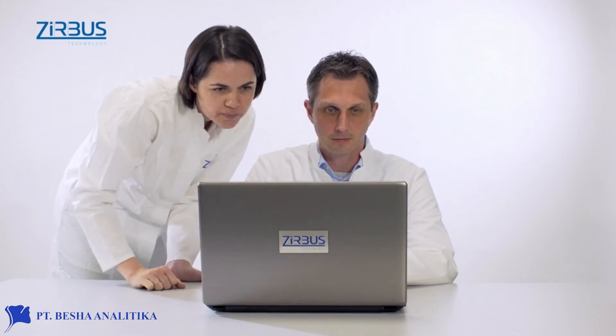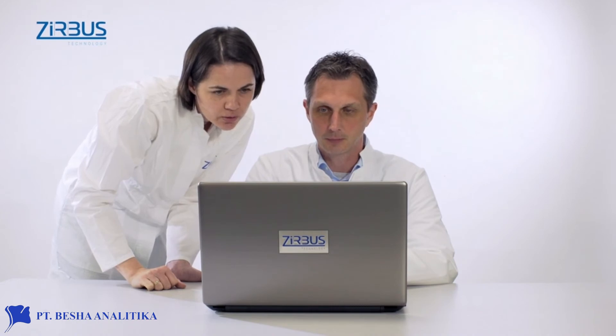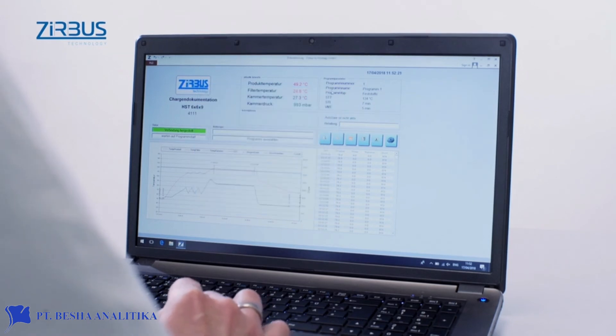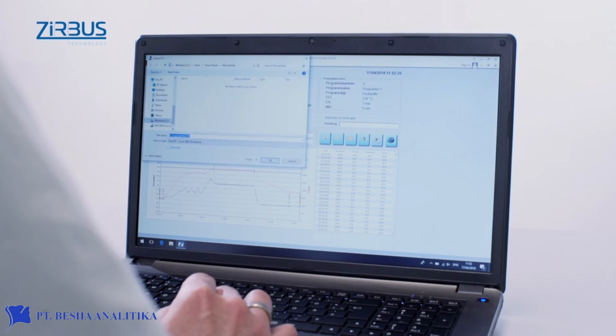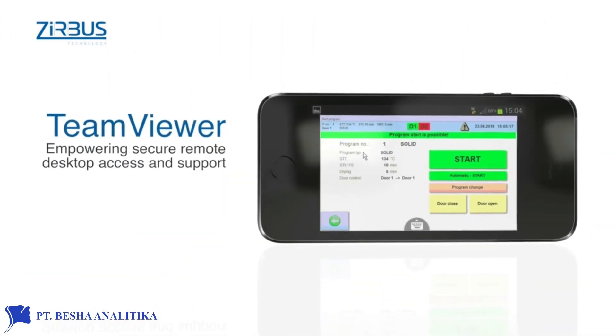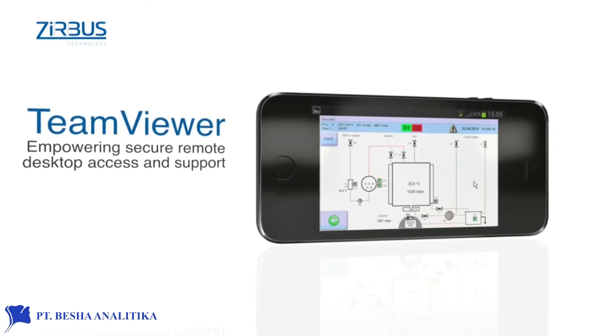The unit can be operated externally using a laptop with a standard ethernet connection, offering a convenient way to monitor sterilization processes from an office, for instance. At the same time, batch reports are documented to provide a detailed analysis of the sequence of steps, and these can be exported as either PDF or CSV files. In addition, TeamViewer allows users to monitor processes from their phone.